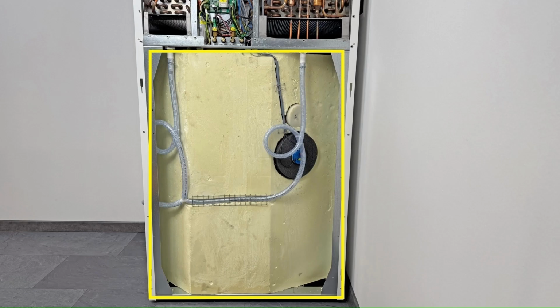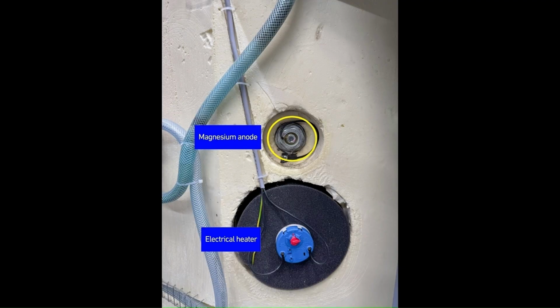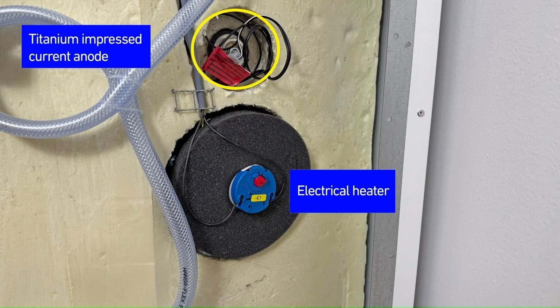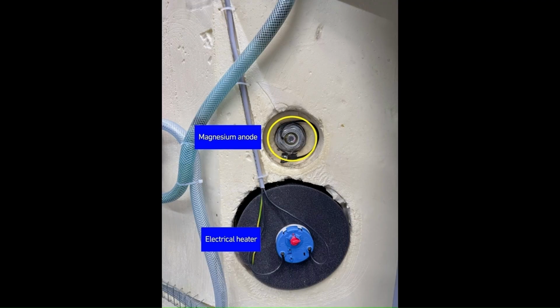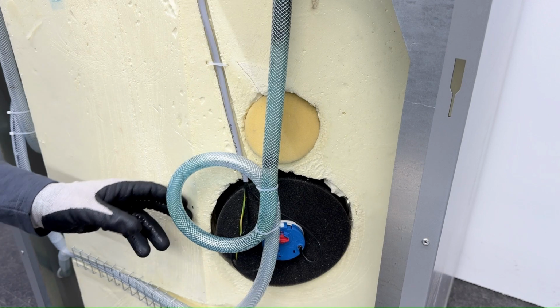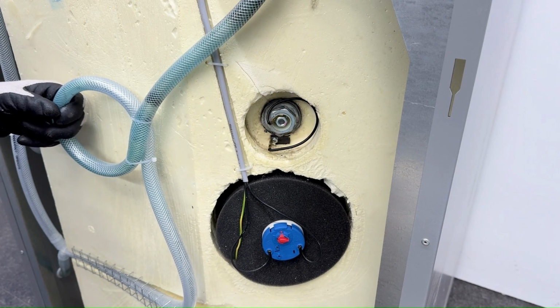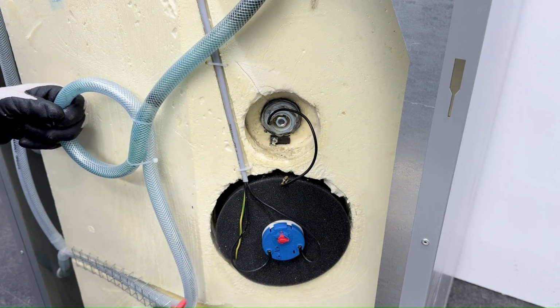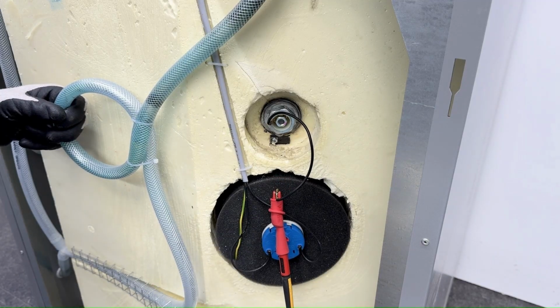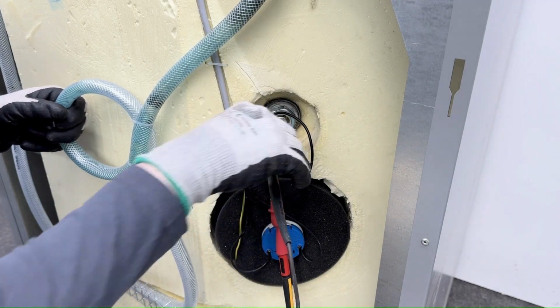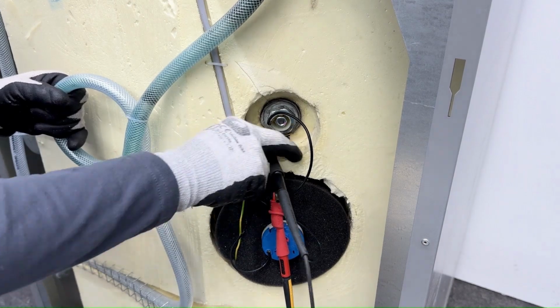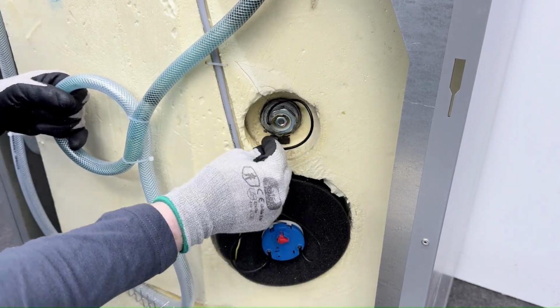Checking the sacrificial anode, which is installed in the hot water tank. PICHLER heat pumps have 2 types of sacrificial anodes installed: magnesium sacrificial anodes for devices with serial numbers beginning with F2207 and impressed current anodes for devices with serial numbers beginning with F2208. Always check the magnesium sacrificial anode when the tank is full. Measure the protective current by loosening the tank's cable and using an anode tester or ammeter, as demonstrated on screen. If it is below 0.3 mA, have the anode replaced. Finally, make sure to reattach the cable tightly to keep the anode working well.